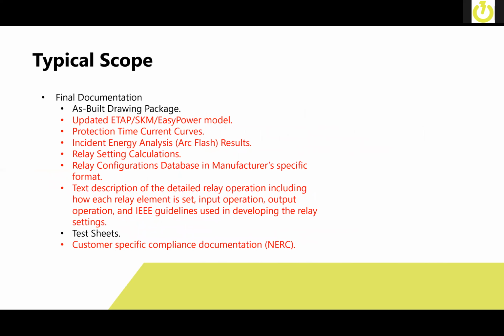From a final documentation standpoint, it's recommended to do as-built drawing packages along with updated ETAP, SKM, Easy Power models in their native manufacturer format. That way you can have it for your records and you can use it for whatever project you have in the future. Updated protection time current curves, incident energy analyses or arc flash results, relay settings calculations, and relay settings configuration database in manufacturer specific format. Again, if you ever have to go back to it in the future, you don't have to download it from the relay or get somebody to come on site to do that. You already have them handy.